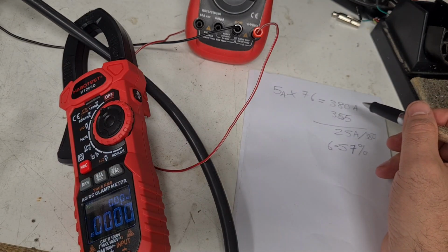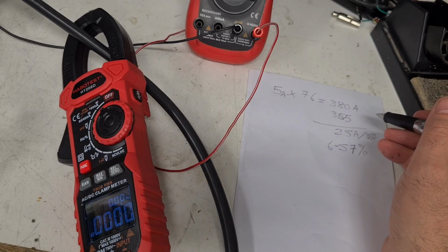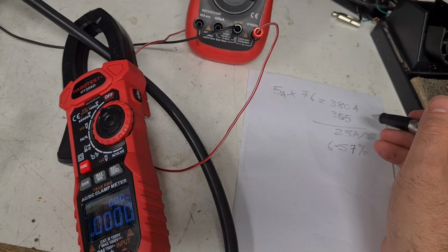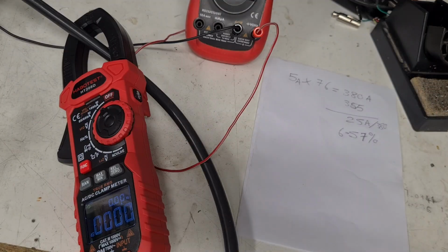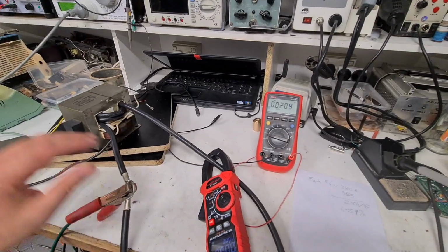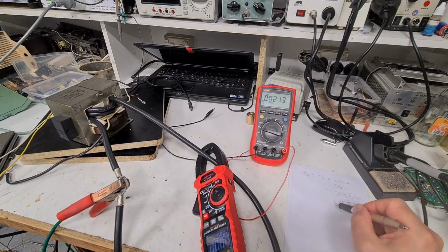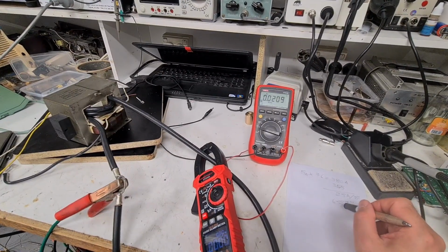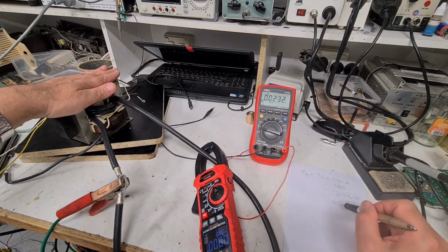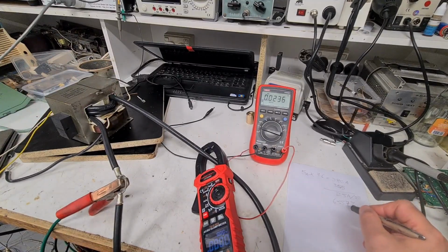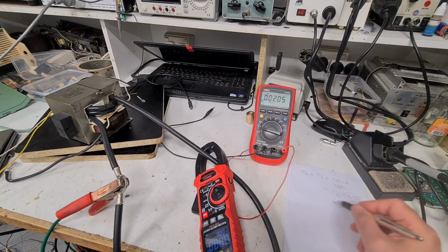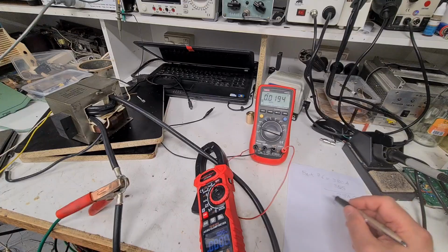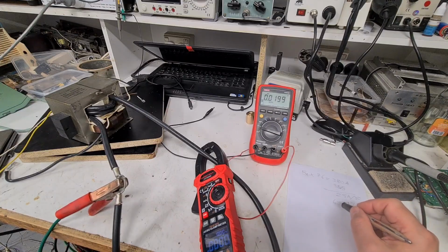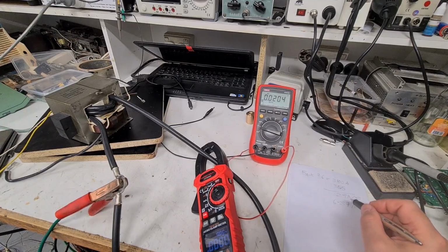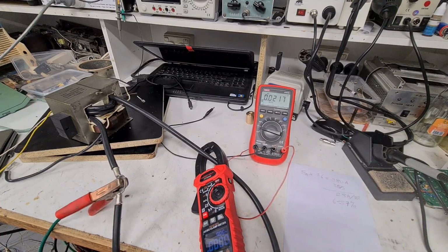So what that tells me is that I actually did research on Google, and they say that you can lose 30%. In this transformer, definitely that's not the case. So this particular transformer, definitely that's not happening. I'm only losing about 6 to 7% less current on the secondary, which again, to gain an extra 7% at a lower current and at a higher current, let's say 6%. And I know if I put more current, I'll do a last test, and I'll try to boost it up to 7 amps or 8 amps, and I want to know what the secondary is. So I'll just do that.